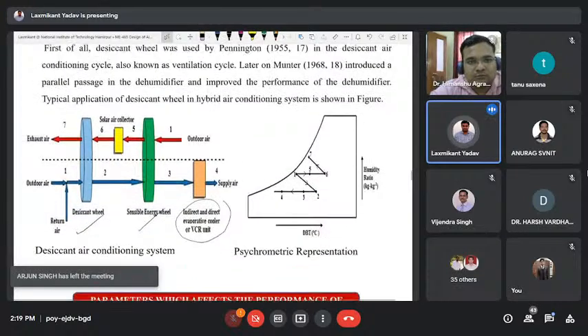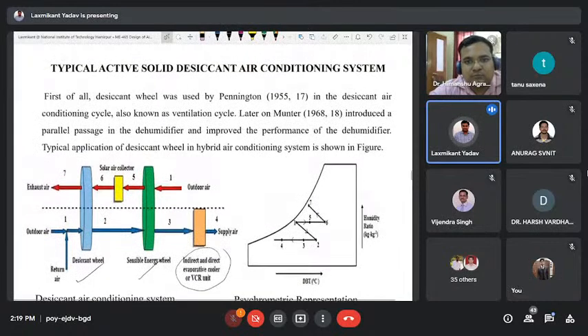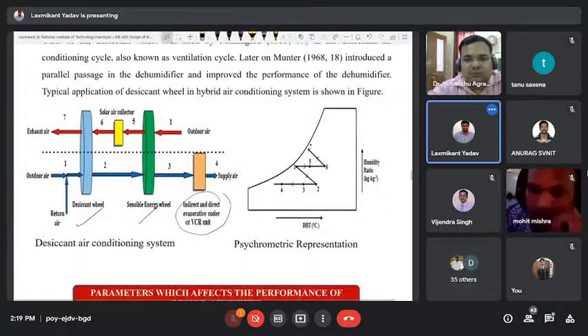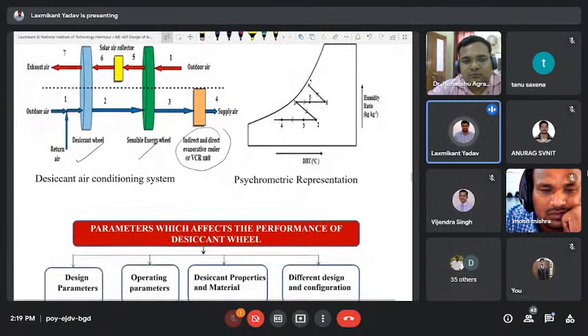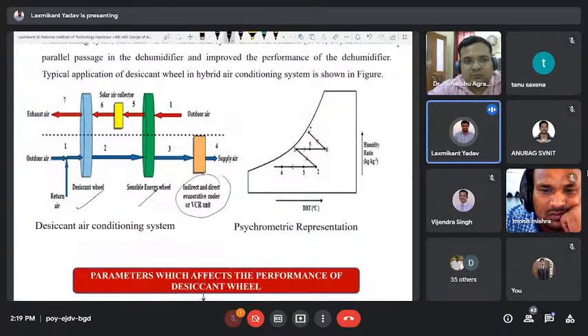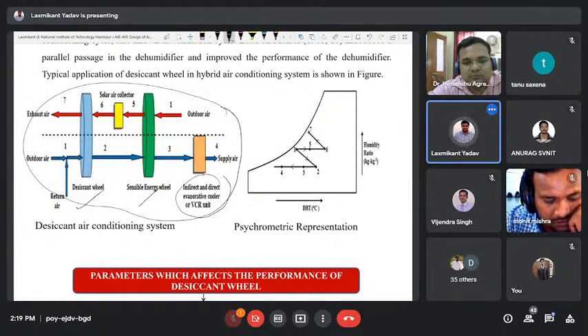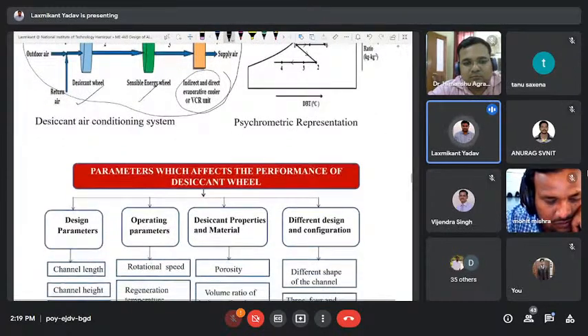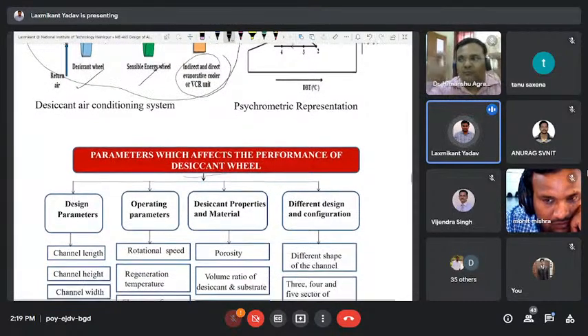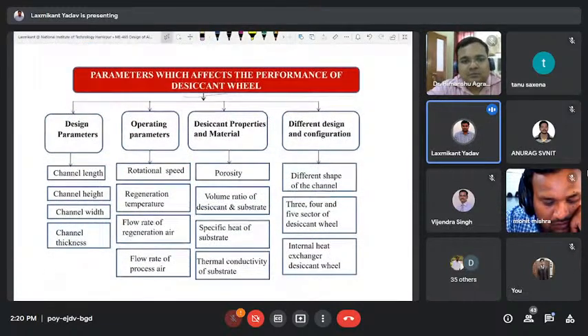So many researchers indicate that the solid desiccant air conditioning system has higher overall COP, and it also saves the environment by reducing the use of refrigerants, because if we use indirect evaporative cooling and direct evaporative cooling for cooling, there will not be any use of refrigerant, so it saves the environment also. Okay, so the parameters which affect the performance of the desiccant wheel are the key areas where research has already been carried out in the field of desiccant dehumidification systems.